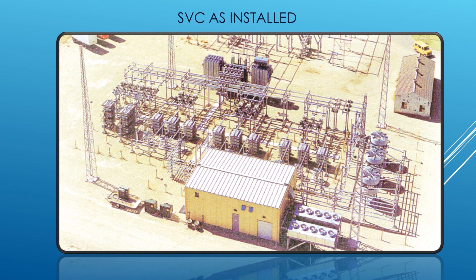This is a picture of the same 500 MVAr ABB SVC as seen on the previous slide. A study was conducted before finalization of any compensation for this site. Based on that study, the alternative solution was to build an additional extra high voltage overhead line, but the SVC cost only a fraction of one extra high voltage overhead line. The construction time is also less, it is less exposed to damage, and the maintenance flexibility with SVC is higher than for the high voltage overhead line.